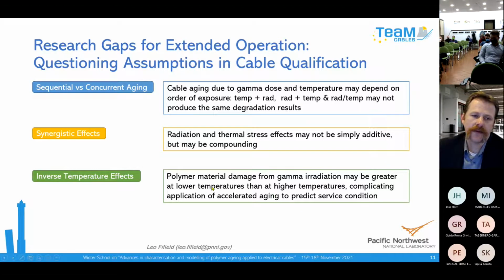Some of the other questions about those assumptions similarly deal with the combination of radiation and thermal aging. During that qualification, it was common to do your accelerated aging by having the cable samples that you're qualifying at an elevated temperature in the oven for some number of days, so maybe at 150 degrees for 21 days, and then expose them to your expected gamma dose, 50 megarads, and then do the qualification test. Well, there's a question: if you're applying radiation stress and thermal stress at the same time, it might activate different mechanisms than if you apply them sequentially.